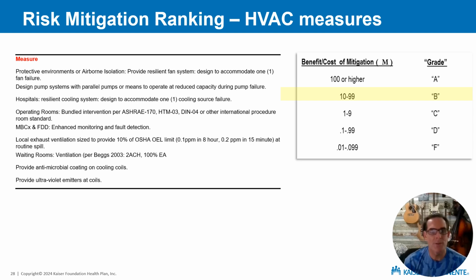And then just under operating rooms, about 6th on this list, I want to point out that monitoring-based commissioning, fault detection and diagnostics is a good investment. That's on this list getting a B, which should make sense, right? Maintenance is a no-brainer, so we can make relatively marginal investments in maintenance and maintenance smarts, and that goes a long way. Back to the example, if you're single and you have a car that takes you to work, you wouldn't buy 2 cars. You would maintain the one that you have, and if there's a marginal investment that you could make to make that maintenance a little bit smarter, then that's going to make a lot of sense.